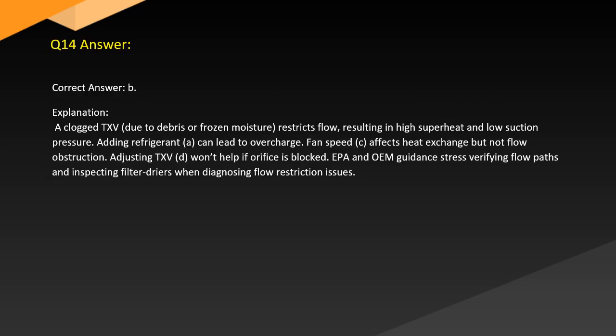Answer. Correct answer: B. Explanation: A clogged TXV due to debris or frozen moisture restricts flow, resulting in high superheat and low suction pressure. Adding refrigerant (A) can lead to overcharge. Fan speed (C) affects heat exchange but not flow obstruction. Adjusting the TXV (D) won't help if the orifice is blocked. EPA guidance stresses verifying flow patterns and inspecting filter dryers when diagnosing flow restriction issues.